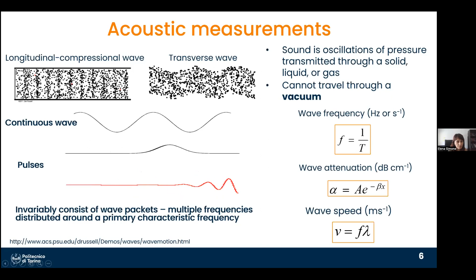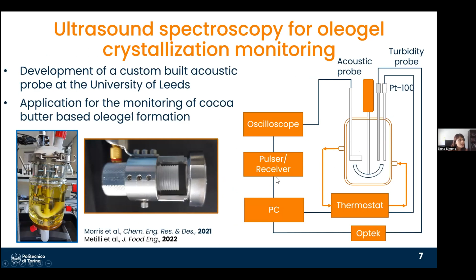We can use continuous waves, but in the case of the work that I'm going to show you, we used pulses. So what we did is we developed a probe using a commercial transducer, and this is a reflection probe. We had a mirror at the end to monitor crystallization. The probe was very simple, and it could be immersed in a crystallizer in order to collect data during the crystallization of the oleogel. What we needed was a source of pulses and then an oscilloscope to read the data.